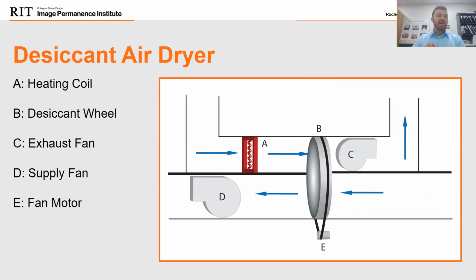I discussed the desiccant air system earlier. We're starting to see more and more of them installed in institutions. And I wanted to cover exactly what that looks like, so if you have any questions about the design of that air system and how it moves. So if you're looking at the desiccant, here's that giant wheel that I showed earlier, and the air is going to move through that unit. The air is going to be brought in through the unit. It's going to come in typically through the bottom vent where the bottom arrows are, across right to left.